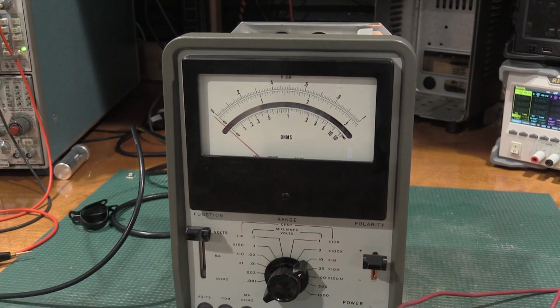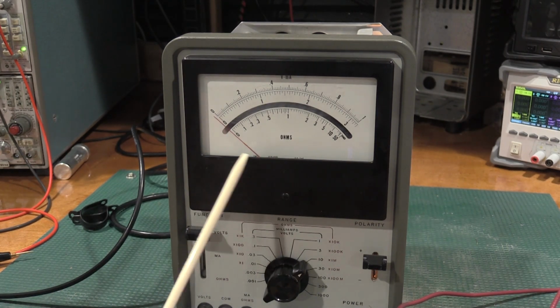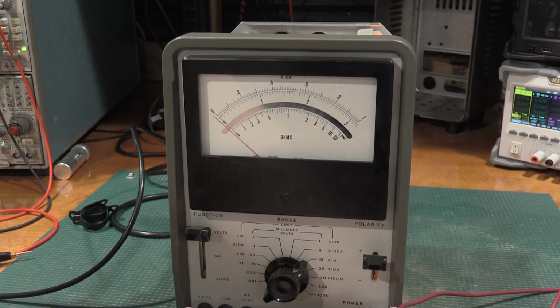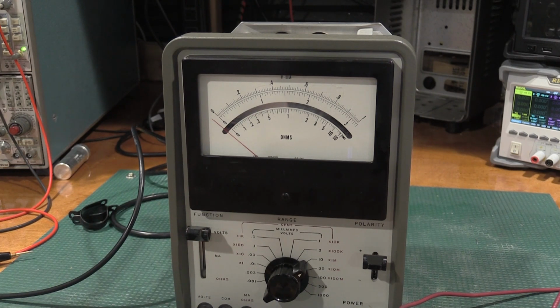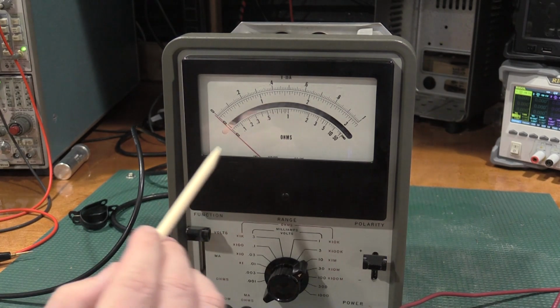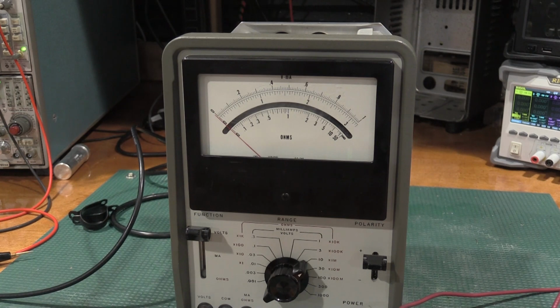Okay, the first thing we need to do on this meter is the mechanical zero of the meter dial, which was actually done, because if I turn this off real fast, we let everything discharge, it will slowly come back to 0. And looking dead on the meter, it is dead on 0. Everything is good to go there. So we have a good mechanical 0. So we'll bring this back up.